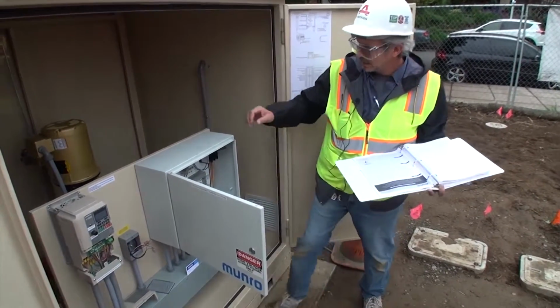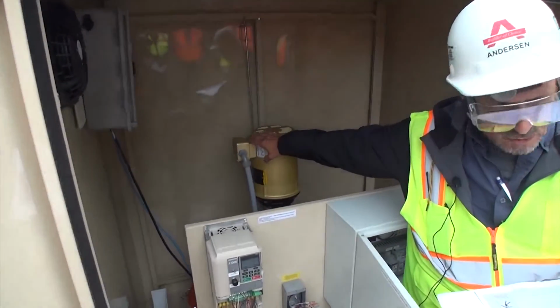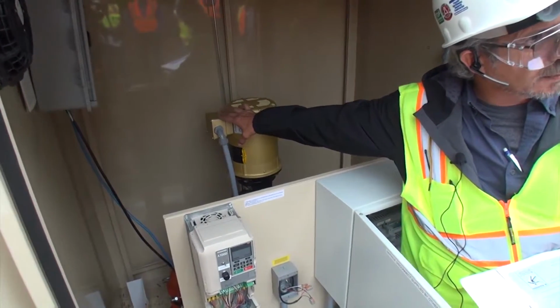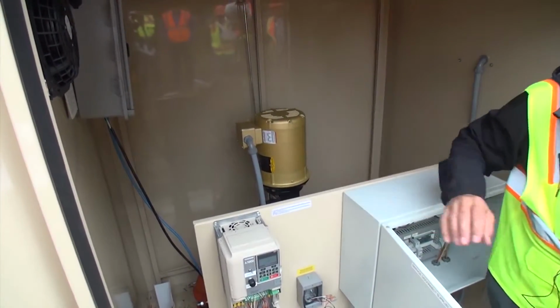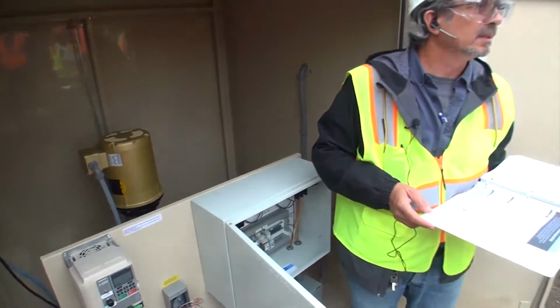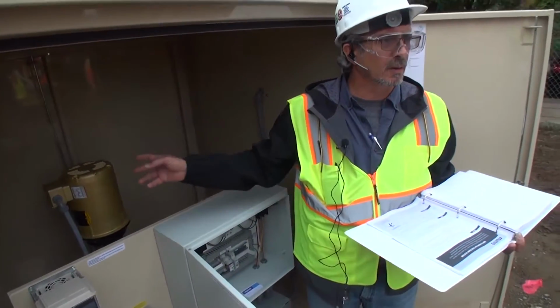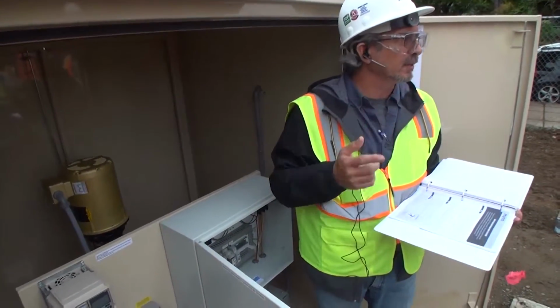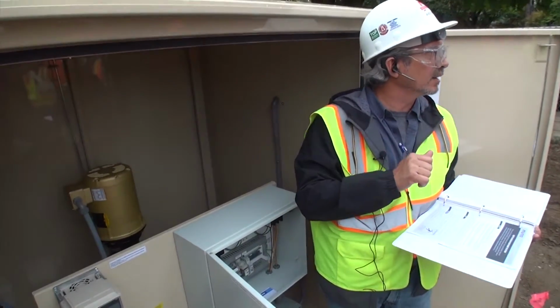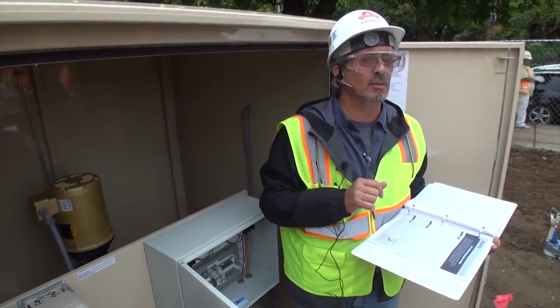T-box connections: where we make the connections to the motor inside this box, we call that a T-box, the terminal box. They're wire nuts, and that is a common place for problems. I recommend that you pull the cover off, smell for burnt insulation, and make sure the wire nuts are tight. I recommend you do that at least once a year.